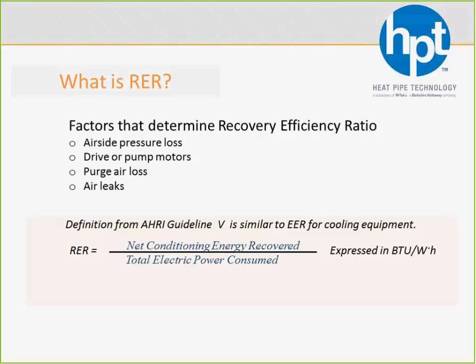It's not just looking at how many BTUs you are getting, but how much energy you are using to get those BTUs. So for us, all we're doing is adding a little static pressure to the system. Again, we don't need any power to operate, so we just add a little bit of static pressure, which means a little bit more fan power is involved to get our BTUs. You compare us to something like a wheel that's adding more static than we are, so even more fan power, but it also has a motor to turn the wheel. You also have to account for leaks and purge and stuff like that. There's a lot more power being added to the system to get those BTUs.